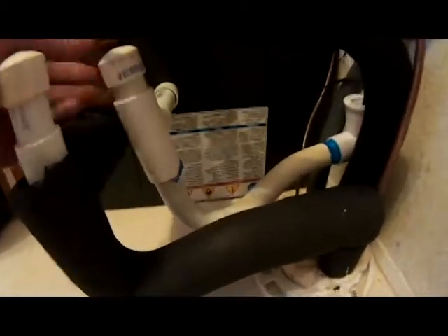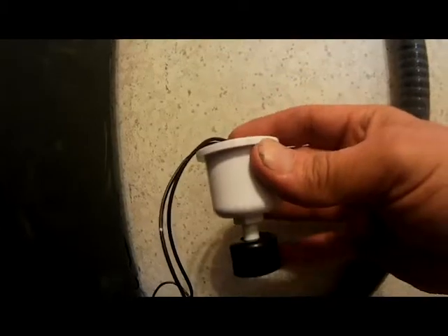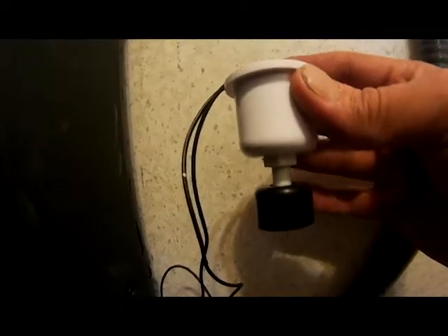Alright, we're at the air handler. Here's your drains here. This is your primary, this is your secondary, and over here you have a float switch that sits down in your secondary line. This thing pops right out. When water rises, it comes up over this float switch, pushes this little black piece up. It's a floater, and that'll basically turn our air conditioner off. So we've got to figure out what's causing this drain line to stop up, to get water in our secondary, and to cause this float switch to trip. So let's go up under the house.